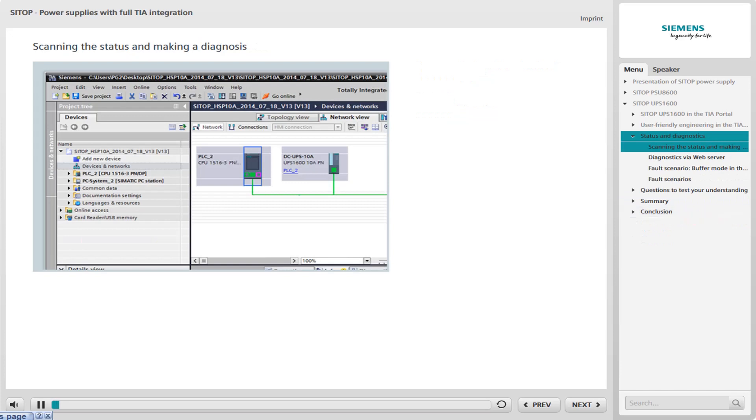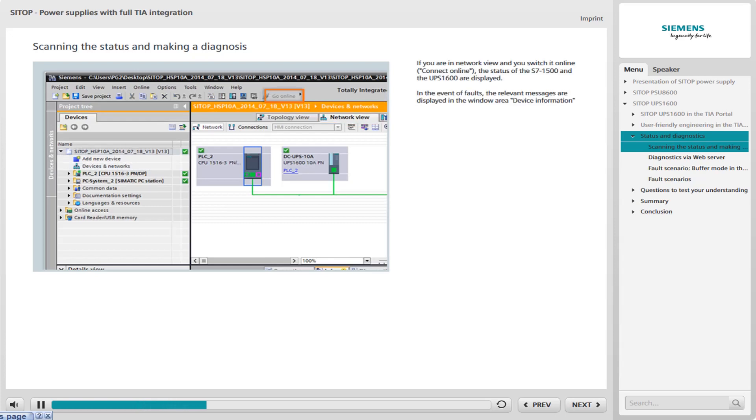You have the option of detecting the status of the controller and the UPS 1600 in the TIA portal. You can also make diagnoses in the event of faults. To do so, change to the Network view tab in the Editor window. Then switch both devices online using the Connect Online button. Either the UPS 1600 or the S7-1500 must be selected for this purpose. The statuses of the S7-1500 and the UPS 1600 are displayed.